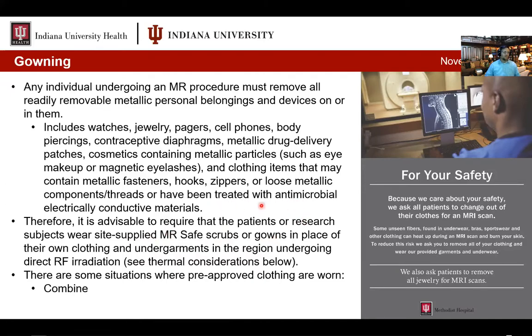These new antimicrobial clothing articles are definitely of concern and something we need to be worried about. There are some situations where there's pre-approved clothing that can be worn. The Combine is one example of this I could think of, where we will get clothing from the Combine. The physicists will take it and do dual energy CT to look for metal in the clothing. We have done high resolution mammography scanning to look for metal threading in the clothing. Sometimes we'll actually do MR scanning to look for susceptibility artifacts. So there are a few cases where non-hospital clothing is allowed.